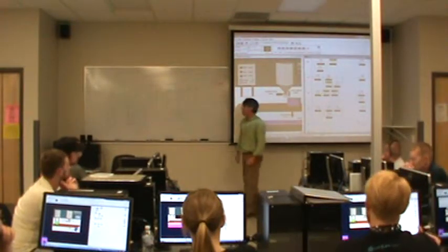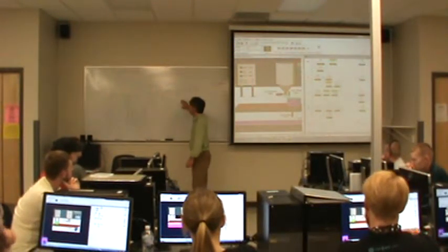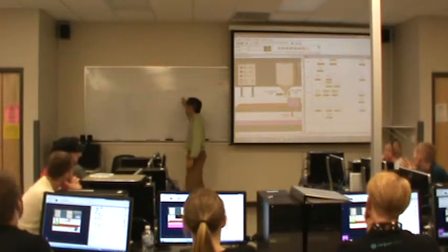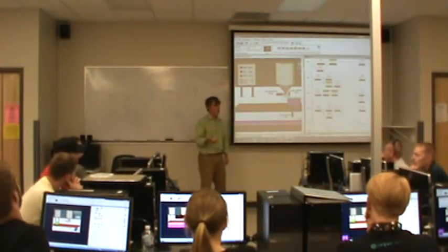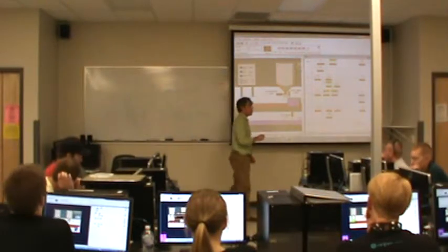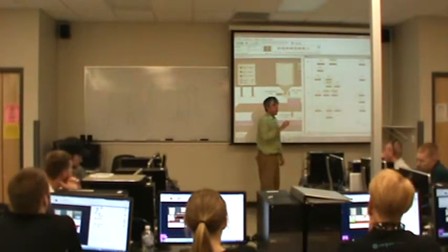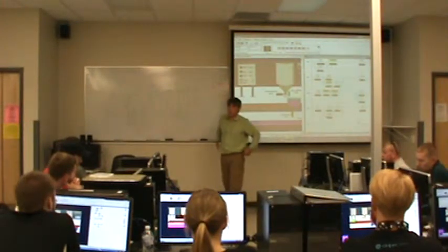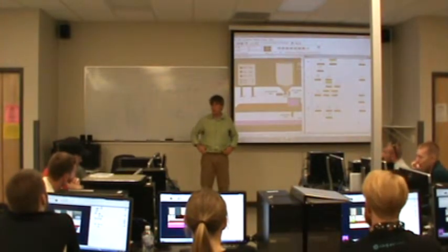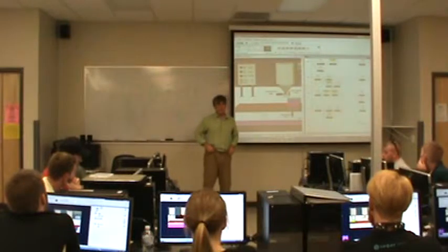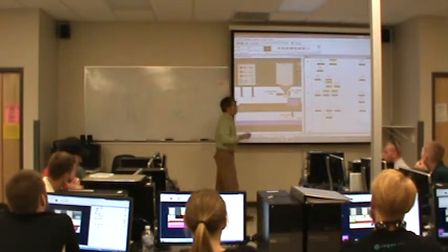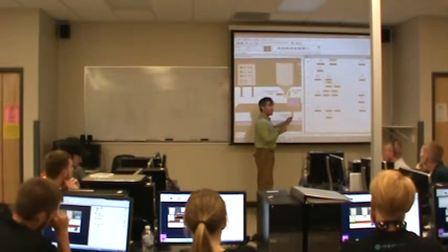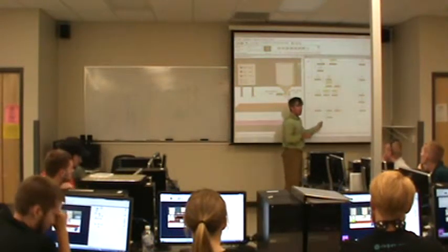Notice in the normal truth table when we're programming an output, we program outputs based on inputs, and we only have to program ones. We don't have to program zeros. If you're programming something with memory, you have to program the zero or what shuts it off. So what should shut off? When should we forget that there's a full box? Box leaves. When the box leaves, right? In other words, when the prox sensor shuts off, that's what should break the seal-in.